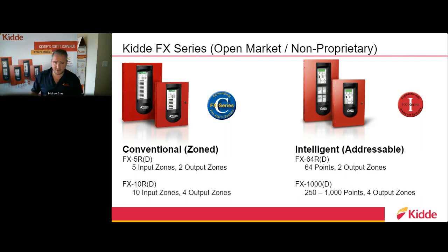Similar on the addressable side, the FX64 has 64 points, any combination of detectors and modules, with 2 output circuits. The FX1000 comes out of the box at 250 points, which has to be 125 detectors or 125 modules, not 126 to 124. The great thing about the FX1000 is that we can scale the system up to 1,000 points.